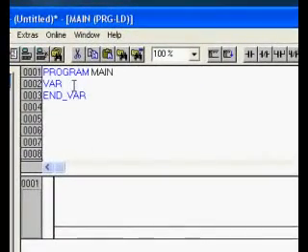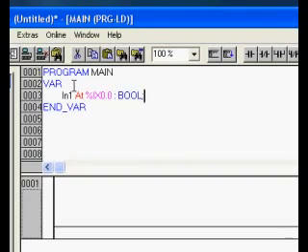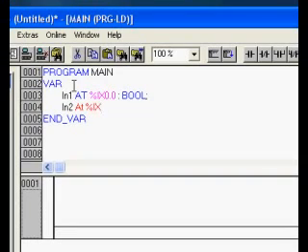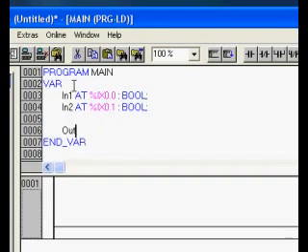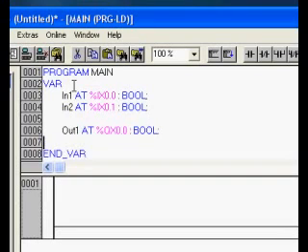Okay, so now the very first step, I'm going to create some variables. TwinCat is tag based, so I'm doing this manually. You can do a table if you want. What I'm typing, I'm creating variables and declaring an address. Now these addresses are just addresses I've made up to use, and you need to do that whenever you're going to link physical I/O. And in order to run TwinCat, you have to have what's considered a sync master, which is at least one physical I/O. So that's why I'm just going to declare 2 inputs and 2 outputs.